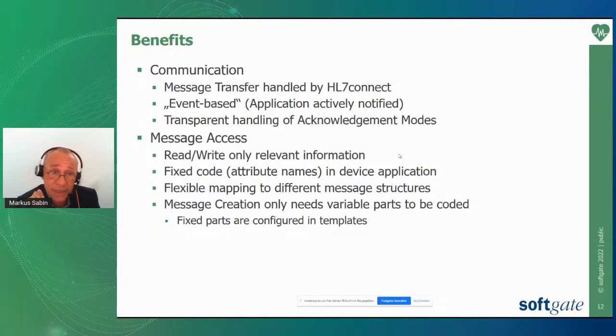You have fixed attribute names in the device application, so you don't have to change the software of your device to adapt to a different HL7 version or a different dialect, as we call it. And you have a flexible mapping of these attribute names to different messages and different message structures. Message creation, we just saw, only the variable parts need to be coded in your device. The rest can be loaded from a template.